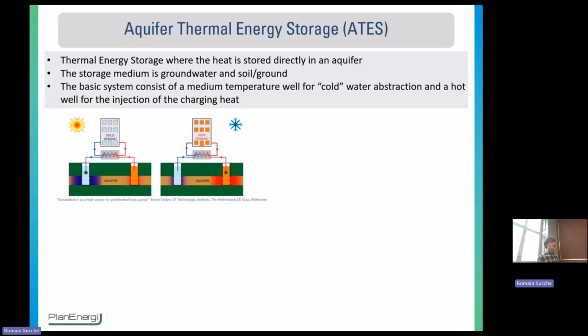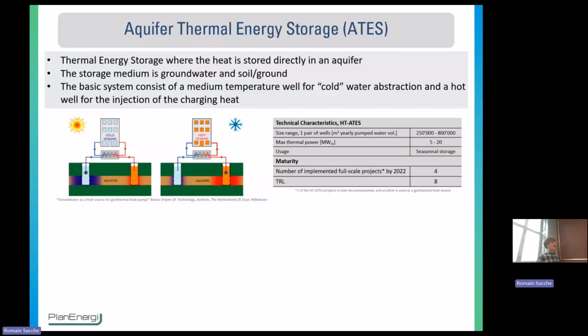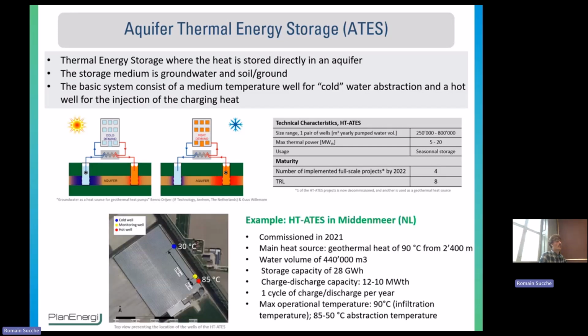And the last one is the aquifer thermal energy storage, which is basically using the aquifers, the groundwater and the soil and ground underground to store heat. And usually there are two wells, one cold and one warm, where you can play around depending on the season to either extract or put heat or cold in the soil, in the aquifer. This can be quite a large system, usually used for seasonal storage, and fairly low thermal power. And the example chosen was the one in Middenmeer in the Netherlands, commissioned in 2021, with a storage capacity of 28 gigawatt hours. And you can see here the two wells, the cold and the warm well, separated by a bit more than 200 meters.